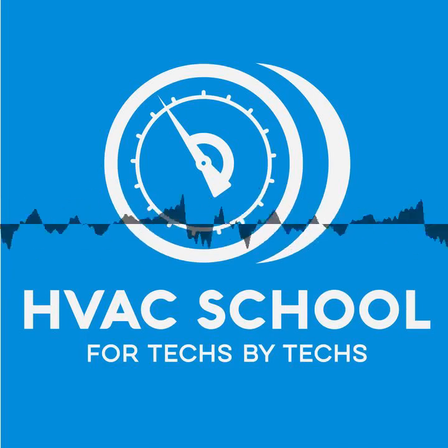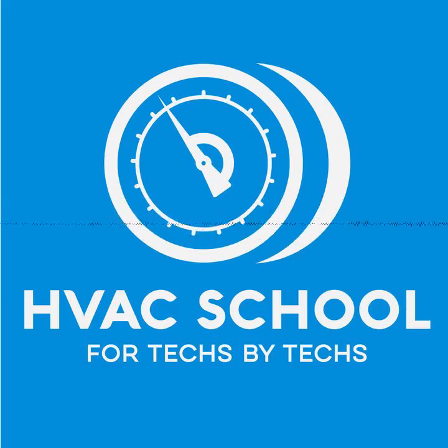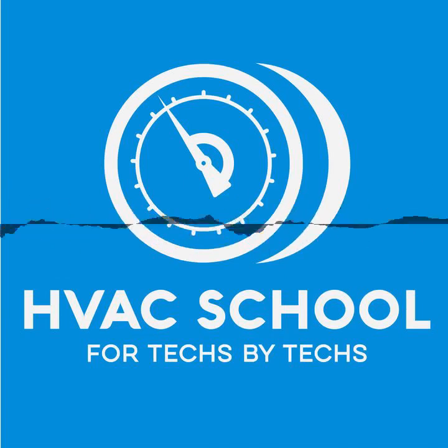Nylog is actually an assembly lubricant. So what it does is it keeps things from galling or binding as you hook them up together. It's just an oil. It's really not a sealant. I don't think it ever dries per se. They may advertise it as a sealant, but it's a high quality assembly lubricant, and it makes sure when the gaskets seat that they're not binding up or anything, and nothing's getting cut.